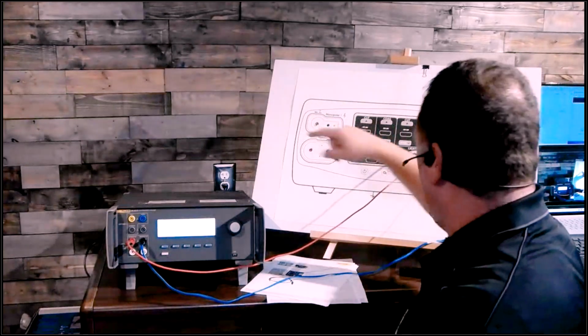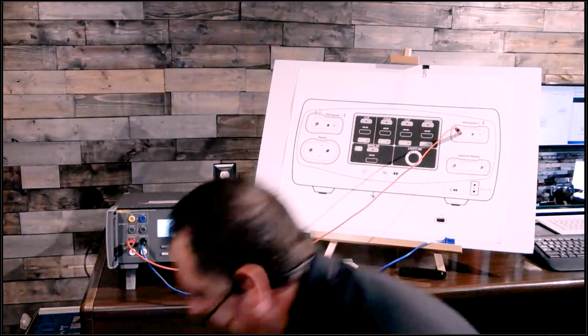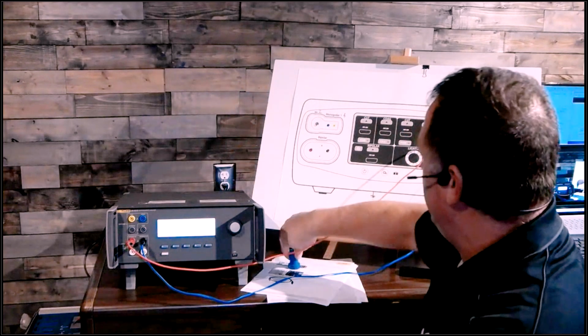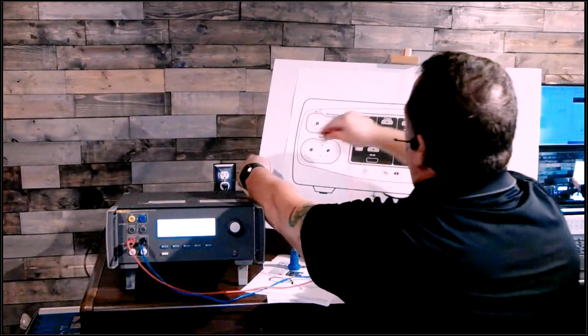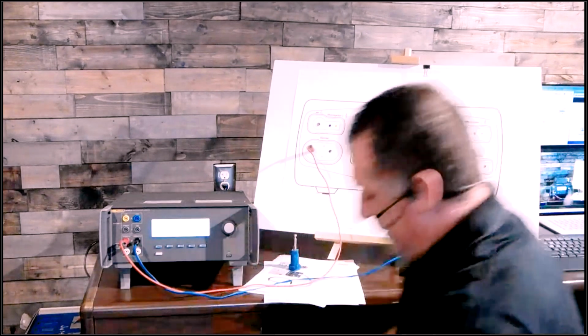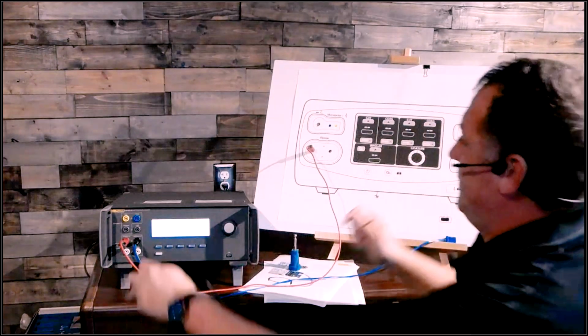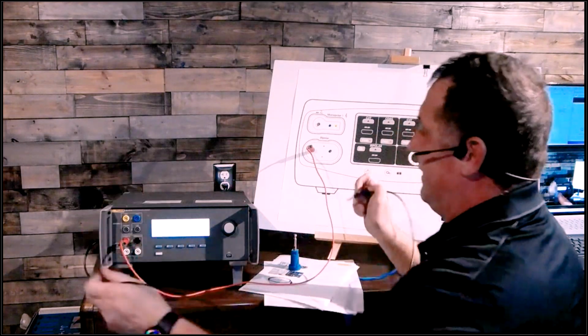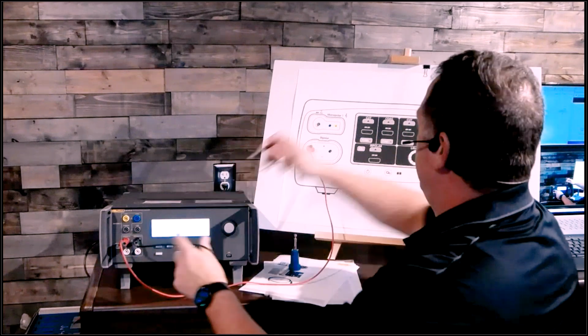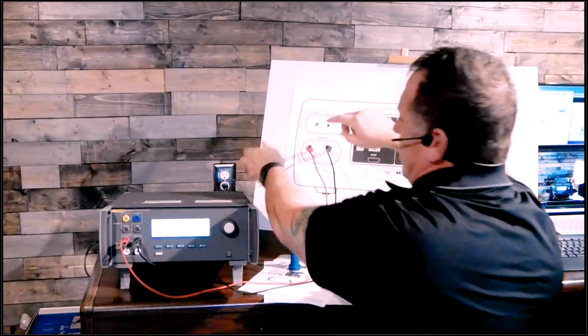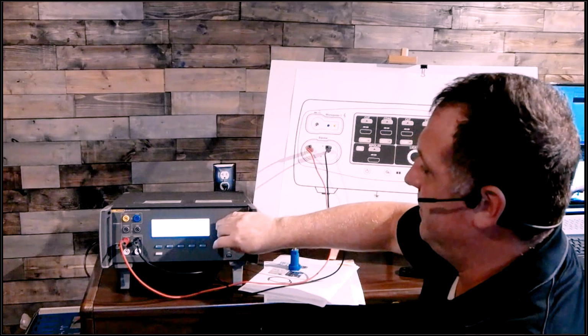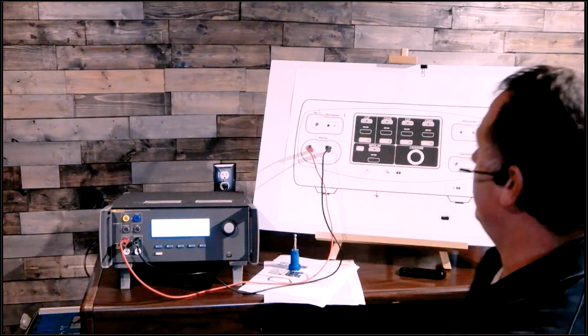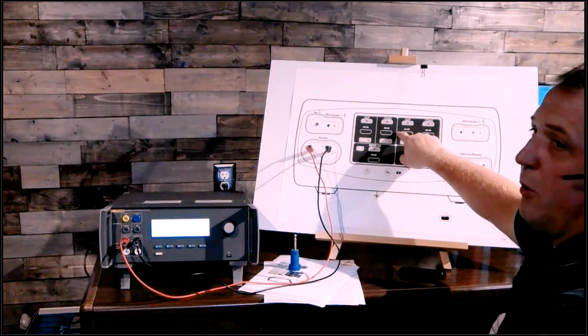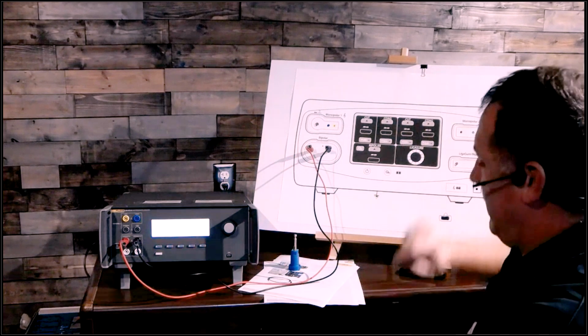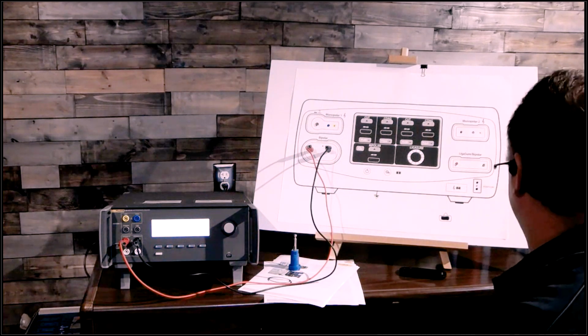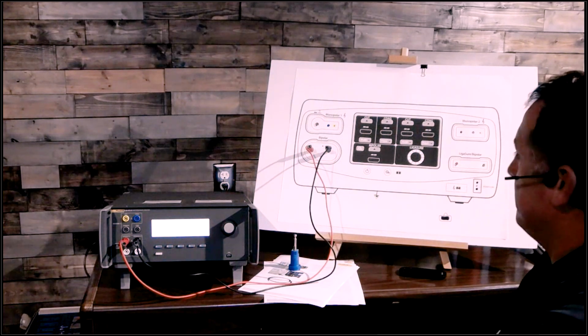Same thing with monopolar 1, but I might need this adapter again, just like before. Same with bipolar - I'll go down to here and do the same configuration as last time. Disconnect this, connect this in, take my resistance down to 50, start continuous here, select the bipolar port with my ESU, select energy, and hit start continuous on my ESU. Stop.